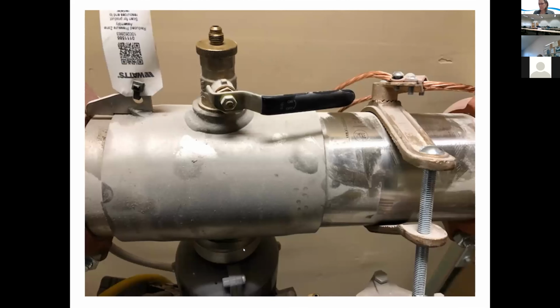So installation is another big thing that you want to look at, because you'll ask them to install a backflow assembly. Does everybody know how these work? This sleeve needs to slide over in order for you to access and repair this backflow assembly. And if you put a grounding clamp right here, how are they supposed to slide this over?